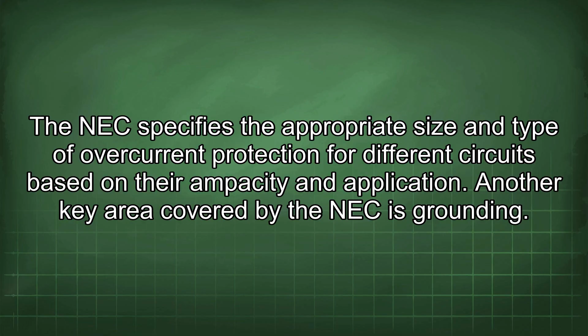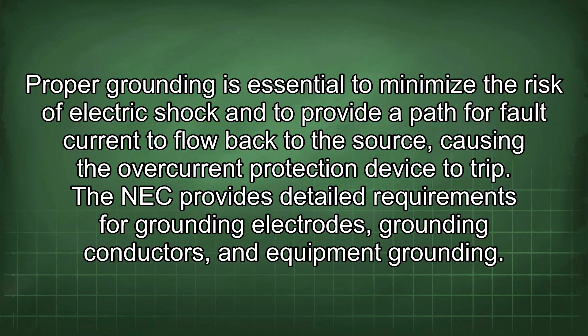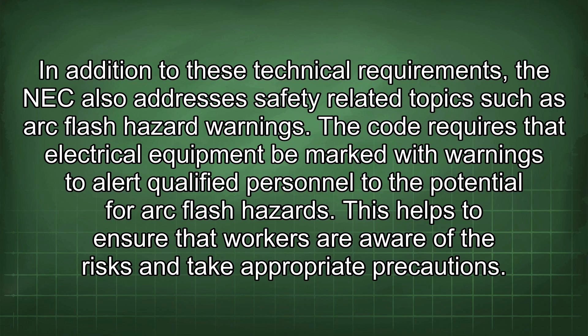Another key area covered by the NEC is grounding. Proper grounding is essential to minimize the risk of electric shock and to provide a path for fault current to flow back to the source, causing the overcurrent protection device to trip. The NEC provides detailed requirements for grounding electrodes, grounding conductors, and equipment grounding. In addition to these technical requirements, the NEC also addresses safety-related topics such as arc flash hazard warnings. The code requires that electrical equipment be marked with warnings to alert qualified personnel to the potential for arc flash hazards. This helps to ensure that workers are aware of the risks and take appropriate precautions.